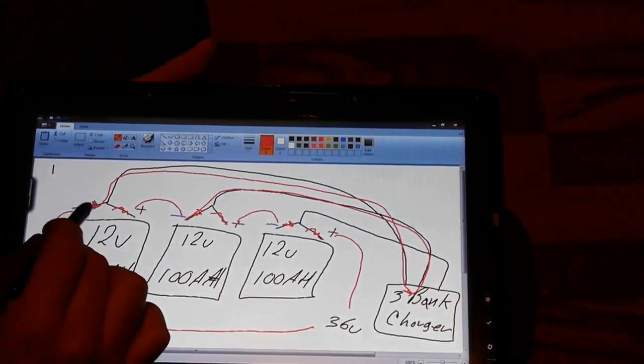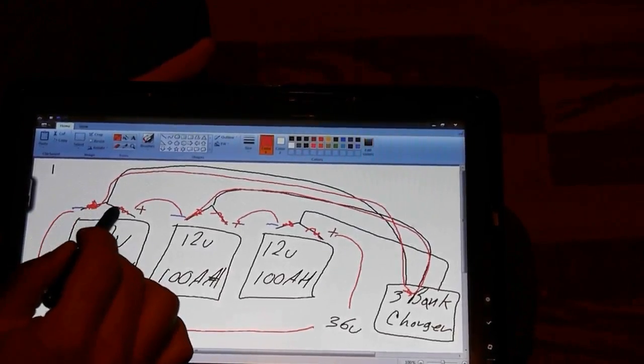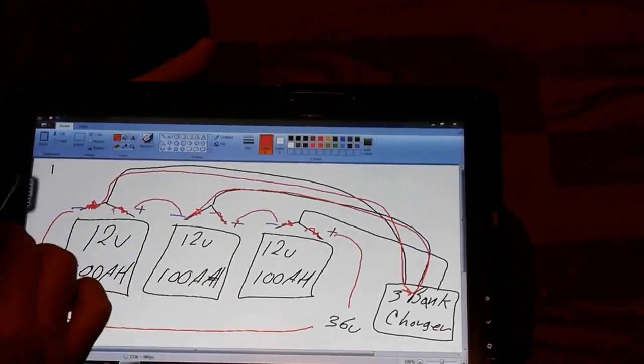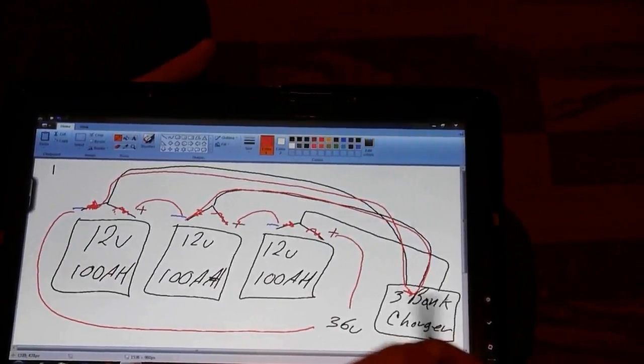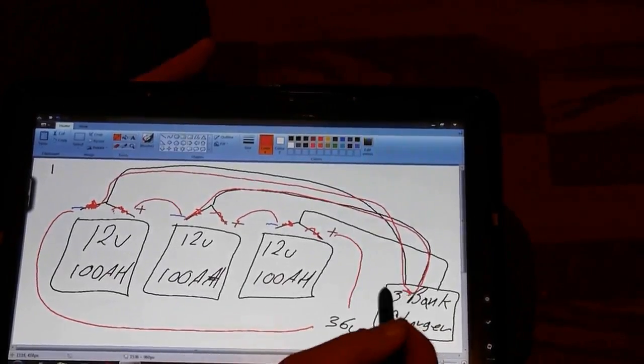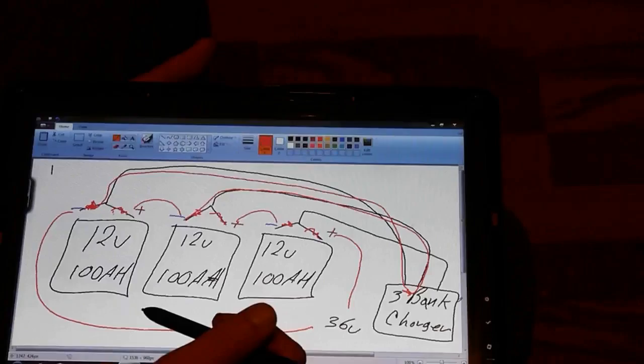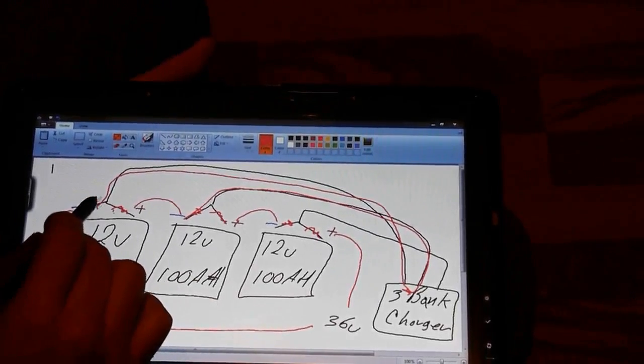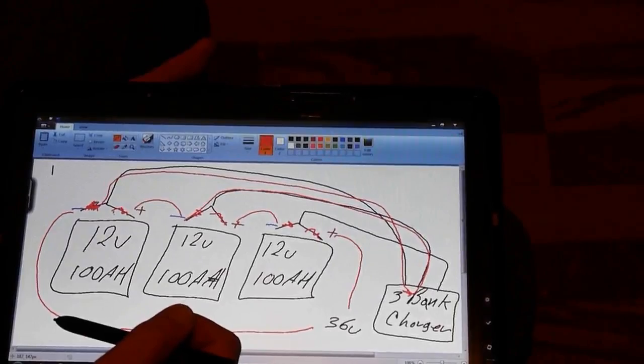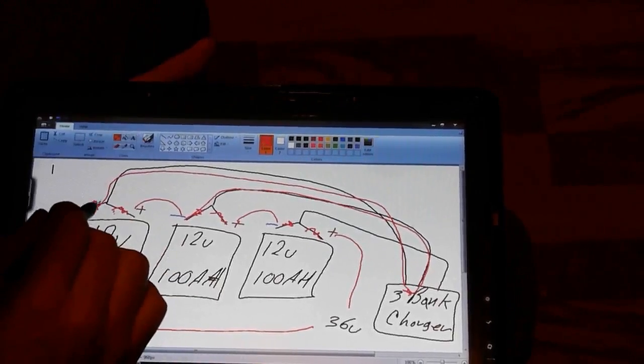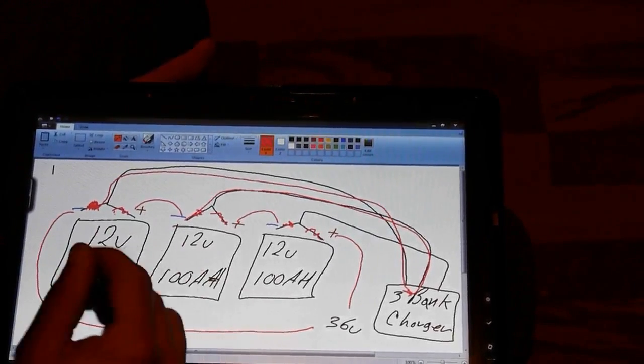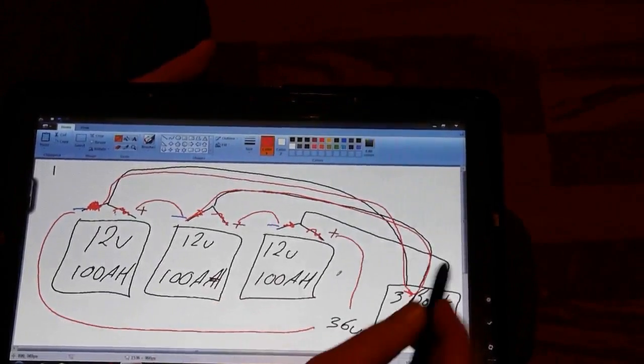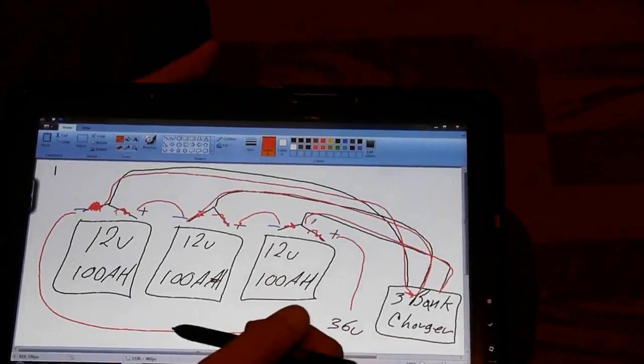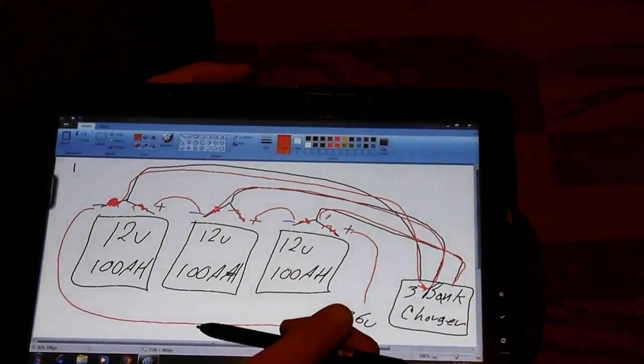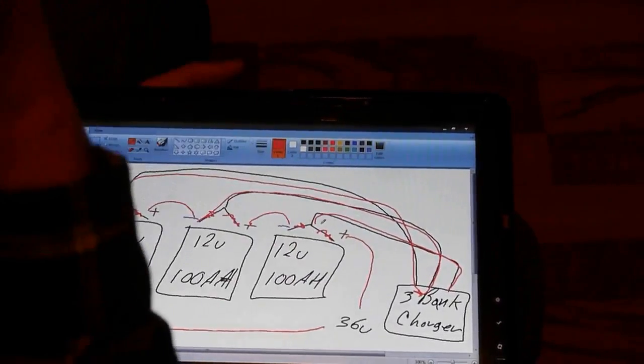I would rate that fuse, if you're concerned about it, the same rating as what's in the positive lead, and you'll be safe there. That way, if anything internally happens inside that charger where your isolation between grounds goes bad, it'll immediately pop that fuse. I don't know why the industry doesn't do it. For the most part, all the chargers I've seen don't include a fuse on the ground side for multi-bank chargers. I think it should be a requirement.